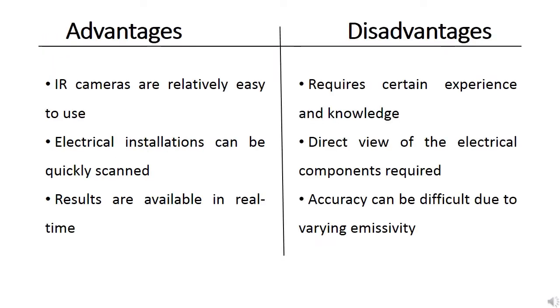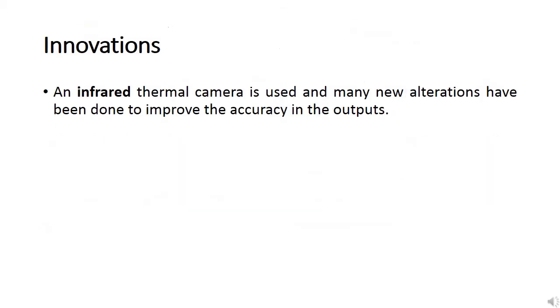Advantages: IR cameras are easy to use, electrical installations can be quickly scanned, and results are available in real time. Disadvantages: requires certain experience and knowledge, direct view of electrical components is required, and accuracy can be difficult due to varying emissivity. Innovations include an infrared thermal camera with many new alterations to improve accuracy in outputs.